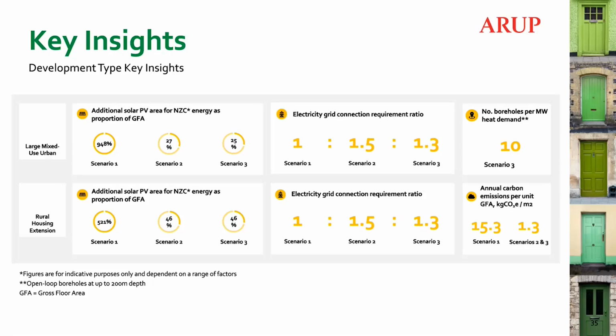Scenario 3 had lower grid connection requirements, mainly due to the fact that the generating technologies, namely the ambient loop network and the ground source heat pump, were found to have higher efficiencies than the technologies for scenario 2, broadly the air source heat pump.